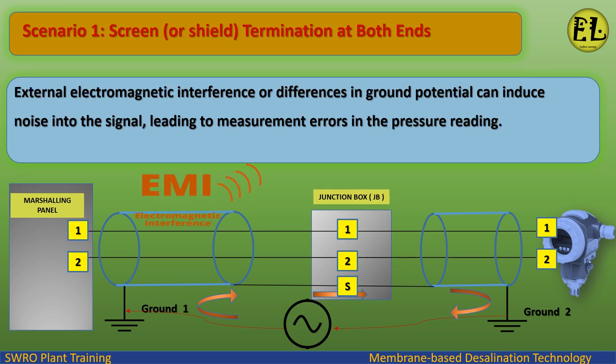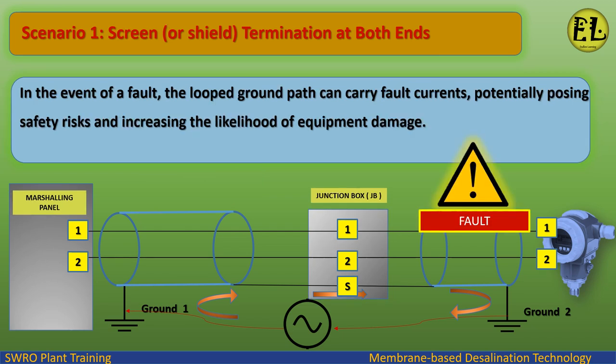External electromagnetic interference or differences in ground potential can induce noise into the signal, leading to measurement errors in the pressure reading. In the event of a fault, the looped ground path can carry fault currents, potentially posing safety risks and increasing the likelihood of equipment damage.